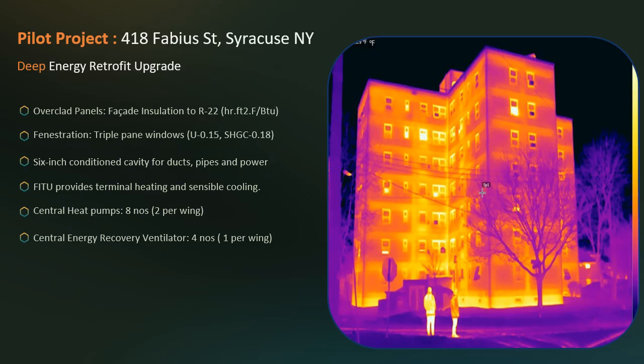So in terms of the upgrade here, we're going to have a facade upgrade, essentially, which is going to upgrade the facade insulation to R-22 levels, with triple pane windows that are going to be applied, 0.15 U value and 0.18 SHGC. Like I mentioned earlier, there's going to be a 6-inch cavity where the ducts, piping, everything is going to run to the units, to the apartments. First, the facade integrated terminal units, which will provide the cooling and the heating to each individual occupiable space.